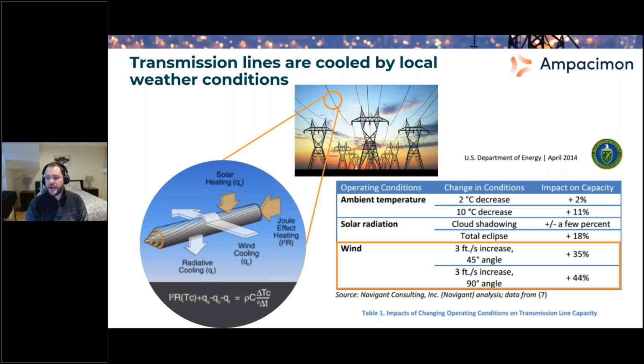But then we look at wind, and with a wind of 3 feet per second, now 3 feet per second is not a gale force wind, it's not a heavy wind at all. If you were to walk down the street on a calm day, that's what you're feeling in your face. It's 3 feet per second or 1 meter per second roundabout. So it's a very light wind, but that can give you up to 44% extra capacity on a typical conductor if it is perpendicular to the conductor. If it is 45 degrees to the conductor, it still gives you 35%. And even if it's in parallel to the conductor, it still gives you some cooling. So the key point here is that all of these different environmental impacts have an impact to how much capacity you can push through the line. But by far, wind is the biggest contributor to cooling and something that is not easy to ignore.